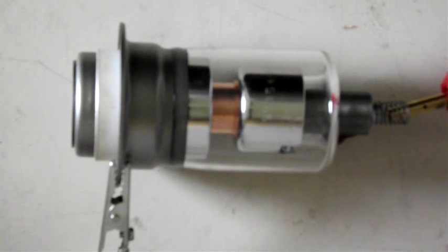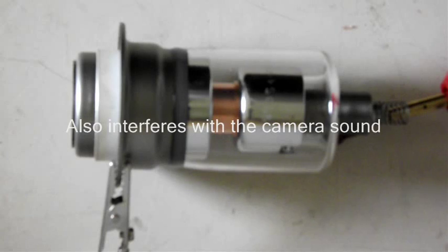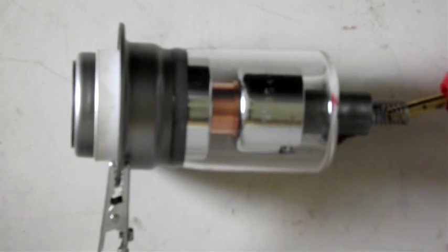At 10kV you can hear the clicking noise of the arc inside the tube. So we've confirmed we've lost the vacuum and we've got a paperweight rather than an x-ray.